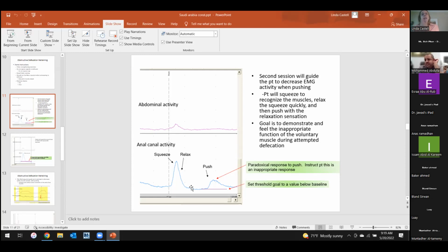Okay, so with anal manometry, usually you position your catheter in the rectum, so all your sensors are in the rectum, and then all your values are based on pressures greater than rectal pressure. So when we do the manometry study, it looks like all of our pressures start at 0 because we zero our channels. But the computer is really basing the 0 value at rectal pressure. So did that kind of answer your question?